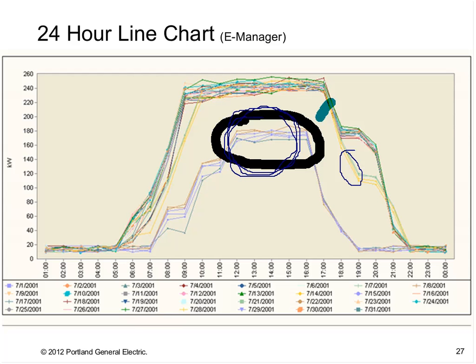So yeah, that looks like an extra day of use, and that is actually weekends. And why would that be, up towards 160 kW when it should be pretty flat? I would call attention to that. Like I said, is someone there on weekends, or is just the HVAC on without lights? I don't know. It's anybody's guess, but that would be a question I would have.